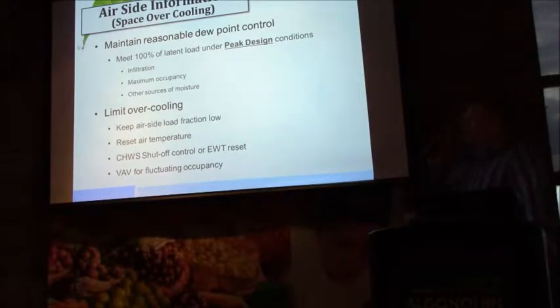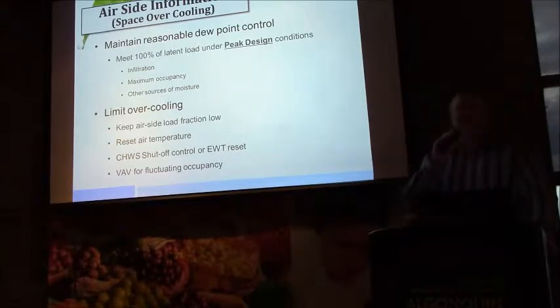When we talk about the control of the latent, we also have to look at any infiltration loads or other latent sources that could exist in the space. And this becomes quite critical because that needs to be added to our latent load calculation when solving for the CFM of primary air at the conditions that we have delivered to the room, to ensure that we offset the latent loads in the space, of course.